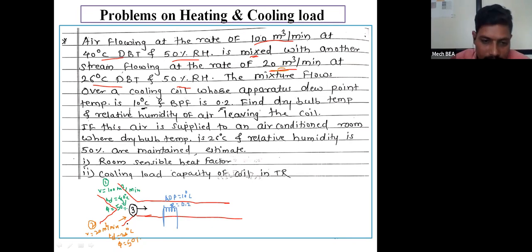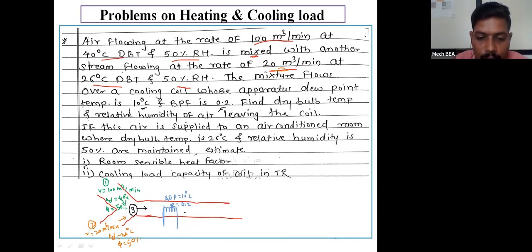So after passing this mixed air, point number 3, over this cooling coil, the property of that mixed air goes on changing. If I consider point number 4, what I have to find out is the dry bulb temperature and relative humidity of the air leaving the coil, corresponding to point number 4.